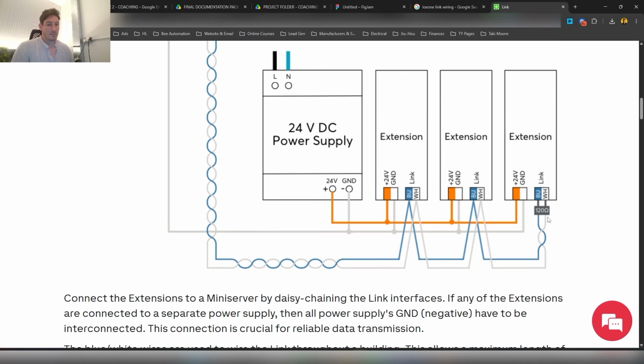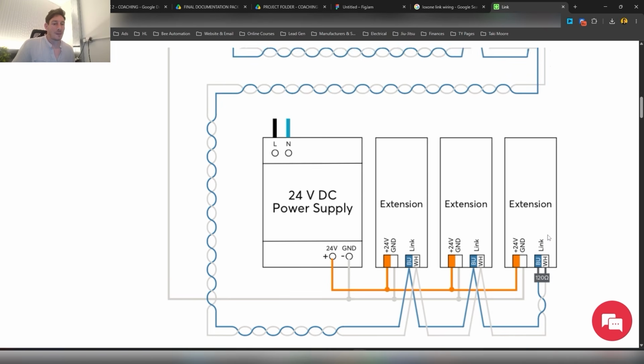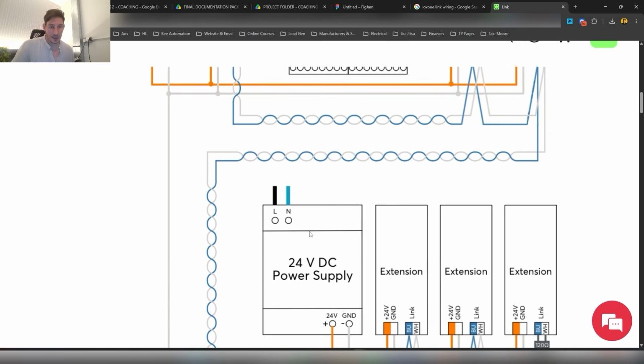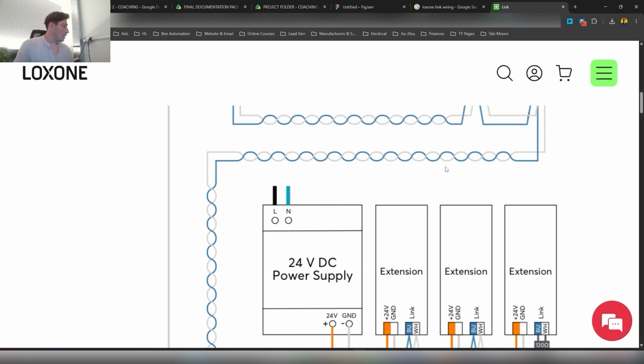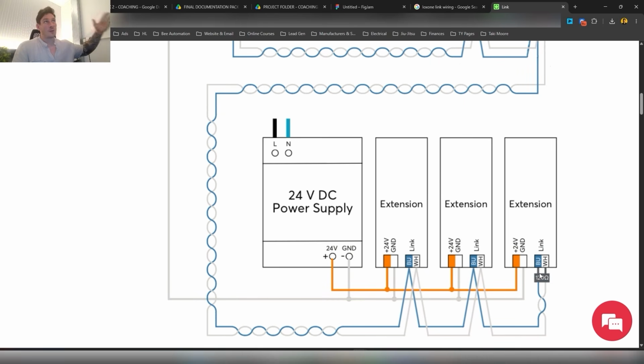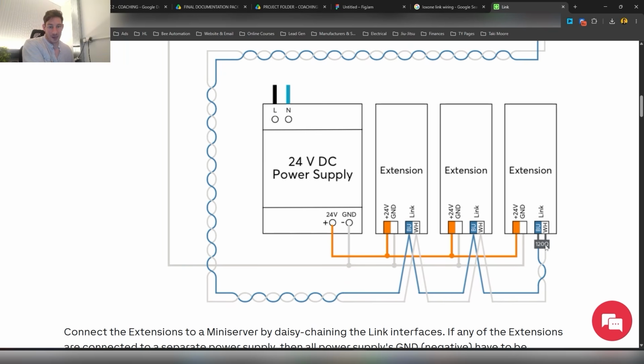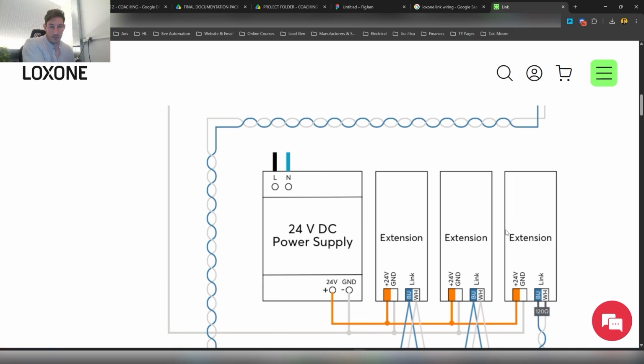Even though that's what's recommended, sometimes you don't have to use a 120 ohm resistor. I can't remember exactly what I found because it's been a while, but what I found sometimes is there's problems when you do a link diagnostic in the software - bad communication on the Loxone link, and you check all your wiring, it's absolutely fine. When you're pre-commissioning everything before it goes on site, in a controlled environment, there's no other variables in terms of wiring in the field and devices out in the field. And you remove this 120 ohm resistor, and then the Loxone Link communication is all green and there's no problem. So it's a bit hit and miss as to whether it's a good thing to use that resistor. It's recommended by Loxone, but the reality is it doesn't always serve the project.